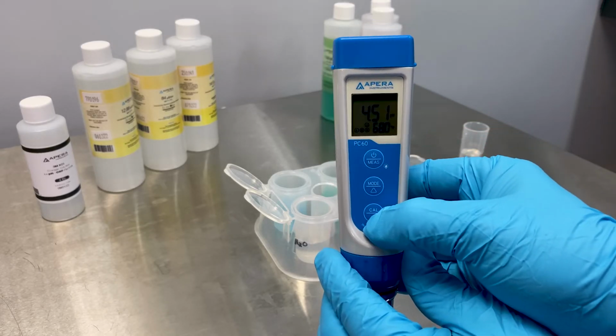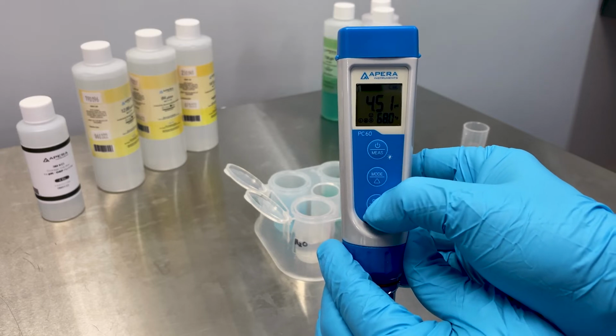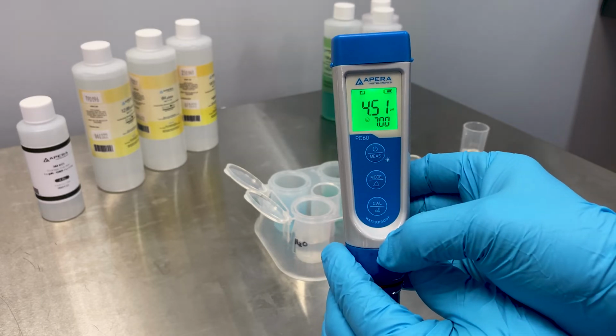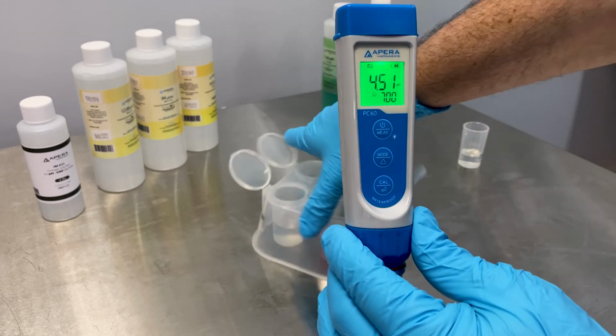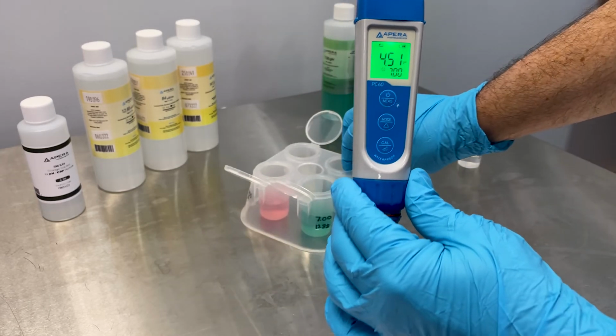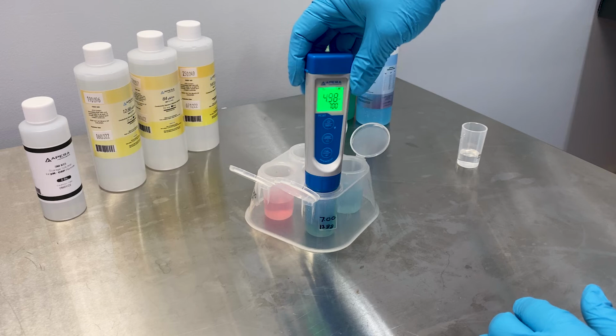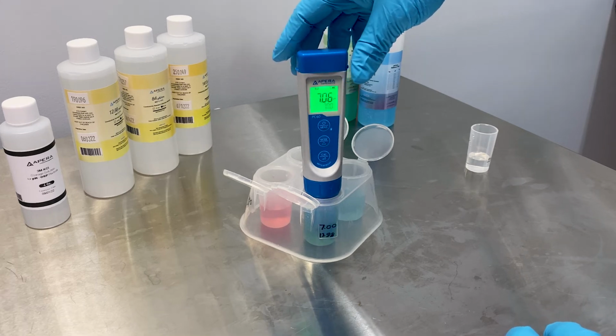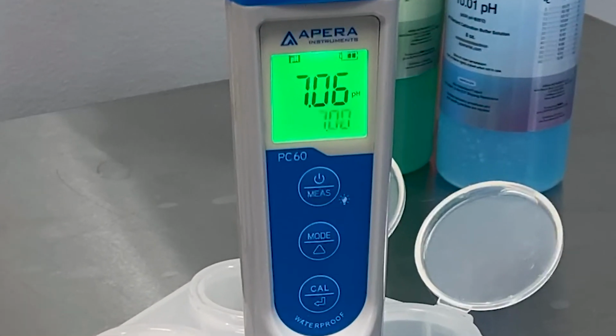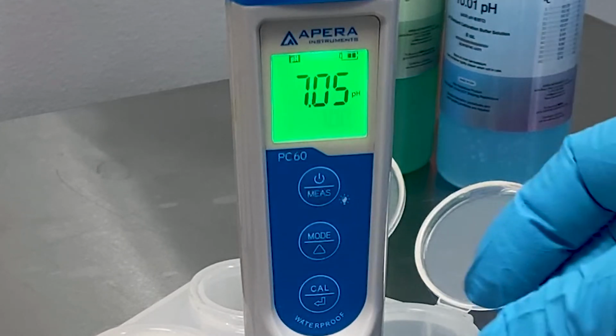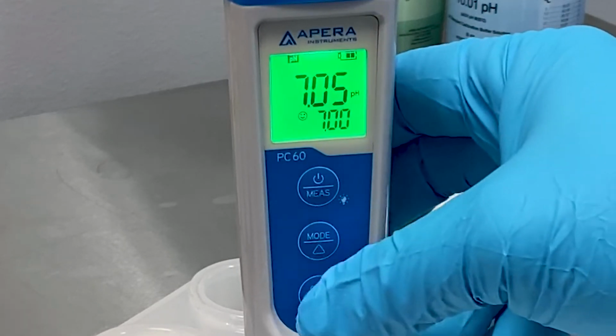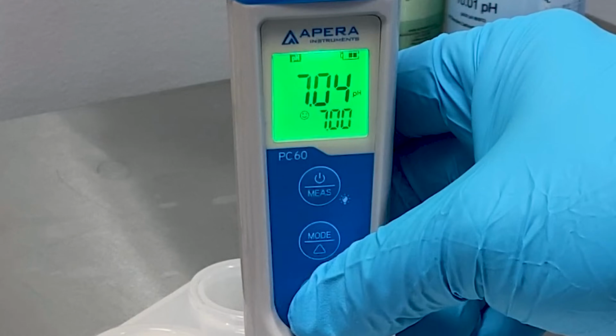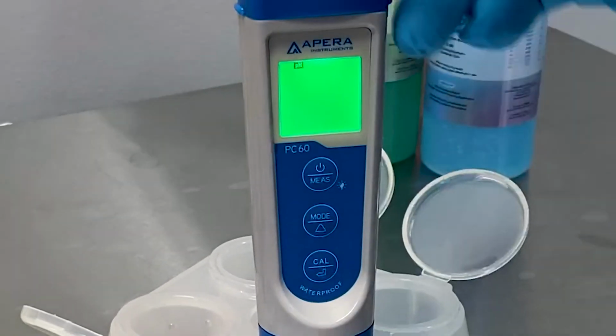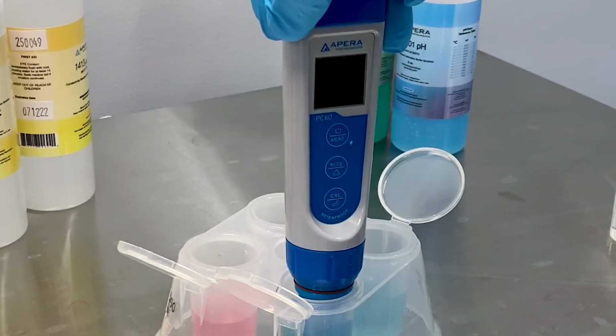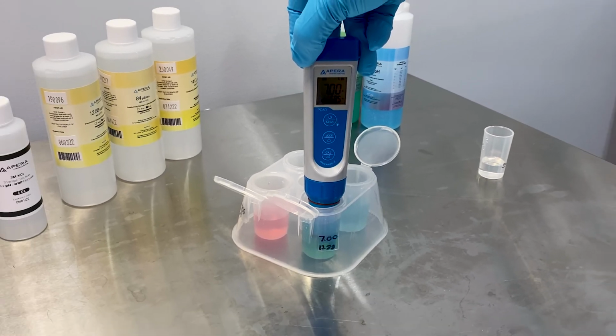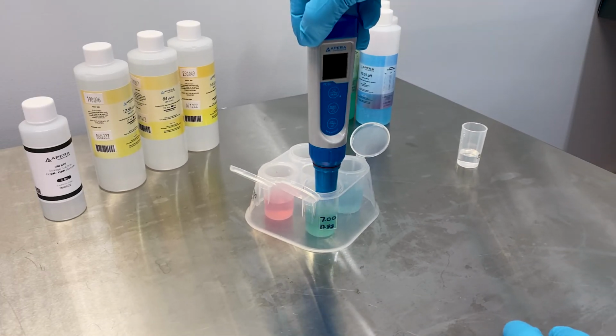Turn on the pH meter and press the calibration button. It should indicate that it's in calibration mode and what number pH solution it's looking for. As you can see, this one is asking for a 7 pH to start. Put the meter in the solution and it should flash or indicate that it's calibrating to that solution. When it's done, it will indicate and give a signal. With this meter, it shows a happy face to let me know I can press the calibration button again to set this calibration and then move on to the next one.